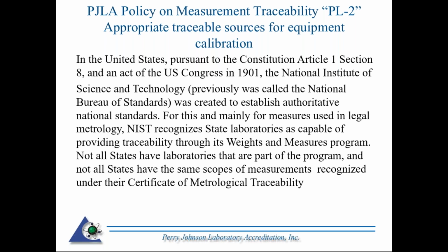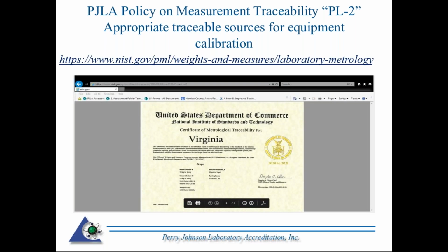Not all have a state lab, state metrology lab. The scopes are not the same for all organizations. However, PL-2, we do recognize them. That program is providing traceable measurements. They have a rather intensive program they put the state metrologists through, depending on what level you are at. As far as training, they have their own system of proficiency or round robins, and we've deemed them as a traceable source.